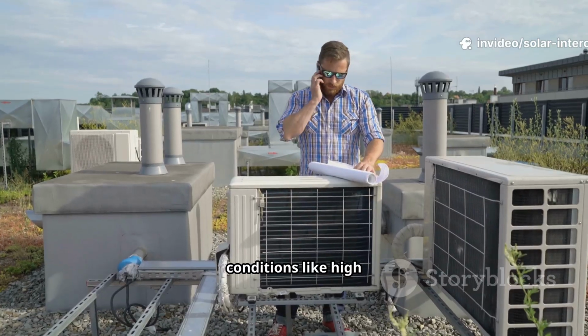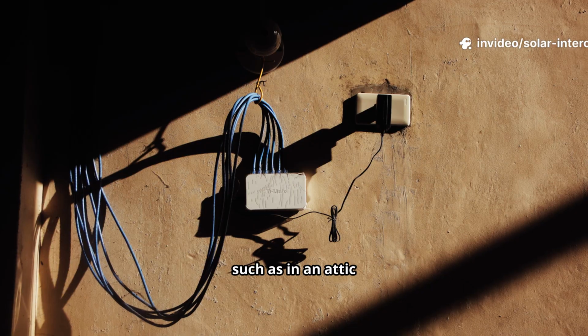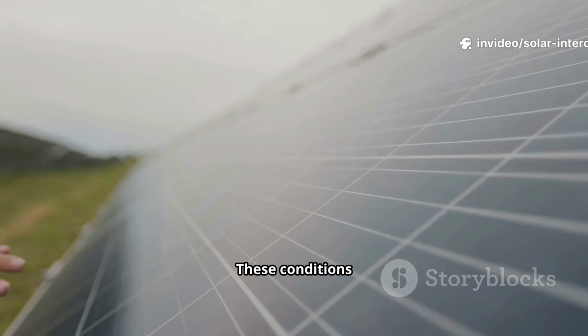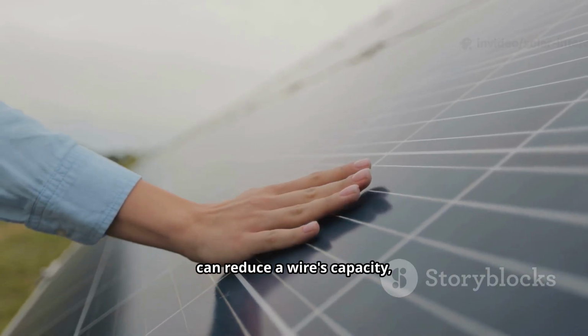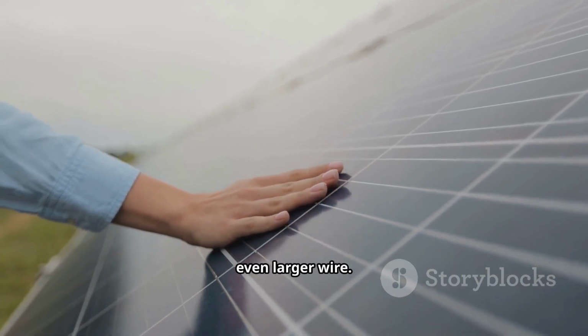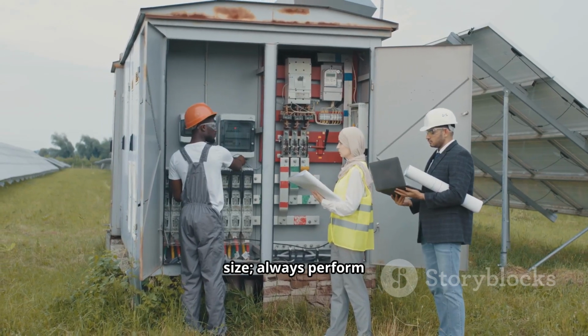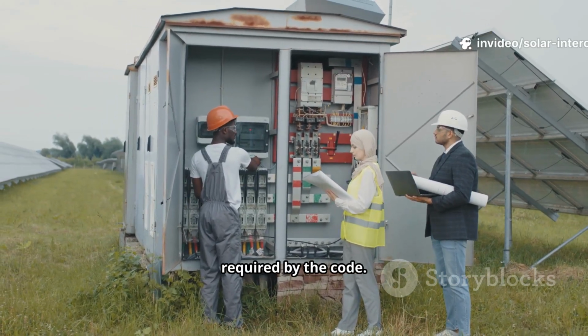You must also account for conditions like high ambient temperatures, such as in an attic or on a hot roof. These conditions can reduce a wire's capacity, so you may need an even larger wire. Never guess on wire size, always perform the calculations required by the code.